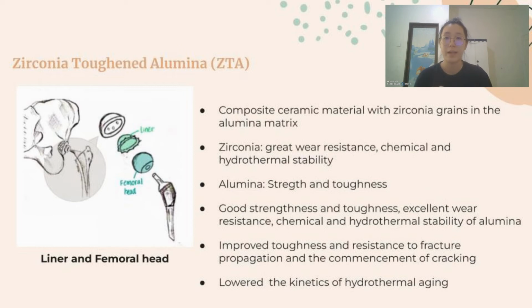So for the liner and femoral head, zirconia toughened alumina, ZTA, is chosen. ZTA is a kind of composite ceramic material with zirconia grains in the alumina matrix that combines the best characteristics of both alumina and zirconia, which are the great wear resistance, chemical and hydrothermal stability of the zirconia, as well as the strength and toughness of alumina. Since base alumina matrix assures high hardness, by adding a fraction of zirconia to alumina results in the composite material with improved toughness and resistance to fracture propagation, as well as the commencement of cracking. Furthermore, ZTA lowers the kinetic hydrothermal aging, which also could be a benefit over other materials.